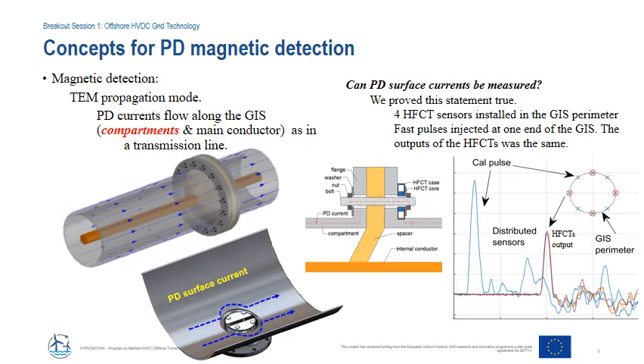We experimentally demonstrated this by inserting high-frequency current transformers in the path of the current from one compartment to the other. As can be seen in the graph, the outputs of the HFCTs overlapped each other. This is a remarkable finding because it proves that the PD current is evenly distributed in the compartment perimeter. Therefore, a certain input current can be correlated to the output of a magnetic sensor placed in the GIS compartments.